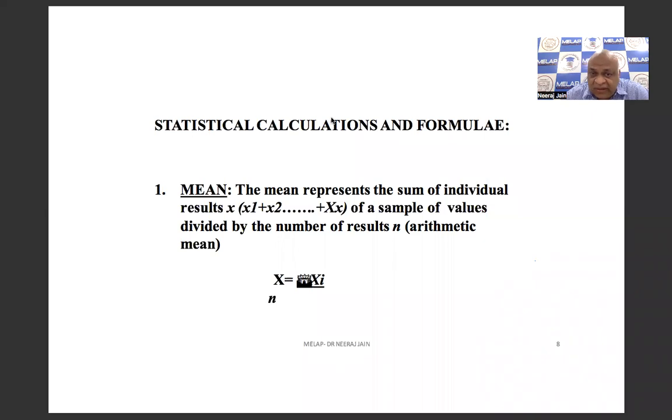Because this mean you are generating in your precision condition. See, your machine is different, wear and tear of the machine is different, calibration of the machine is different, storage of calibrator, reconstitution of calibrator, quality of calibrator, similarly controls. Similarly, reagents, water quality, observer, so many variables are there, environmental conditions. You are taking into consideration all these variables and you are calculating your own mean. What you have to do is check that your mean is not significantly different from the manufacturer mean.